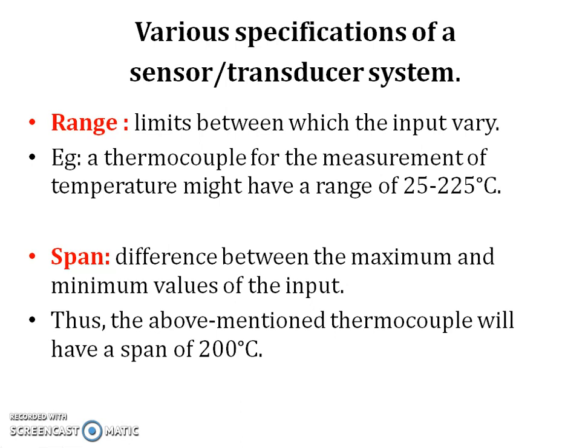The various specifications of a sensor transducer system. Range is the limits between which the input can vary. For example, a thermocouple for the measurement of temperature might have a range of 25 to 225 degrees Celsius. Span is the difference between the maximum and the minimum values of the input. Thus, the above-mentioned thermocouple will have a span of 200 degrees Celsius.